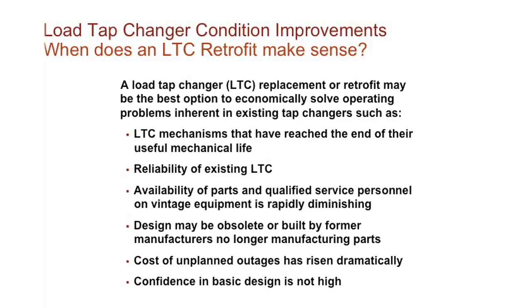Talk about retrofits for a moment. Replacement may be the best option when it's economically going to solve the problems that are inherent to some of the LTCs. It may be you're uprating the transformer, or you may have an LTC that is just, in some cases, better taken off because of the parts pieces inside it. You have to replace the whole LTC. The parts list becomes almost as expensive as a retrofit, or sometimes even more than the retrofit itself. And you're better off going with today's technology, because it's reached the end of its useful life, or reliability in some cases. A lot of tap changers may have hit their maximum number of operations. Some of them are 500,000, so that's what we call the end of their useful life, so you don't really have an option but to perform a retrofit.